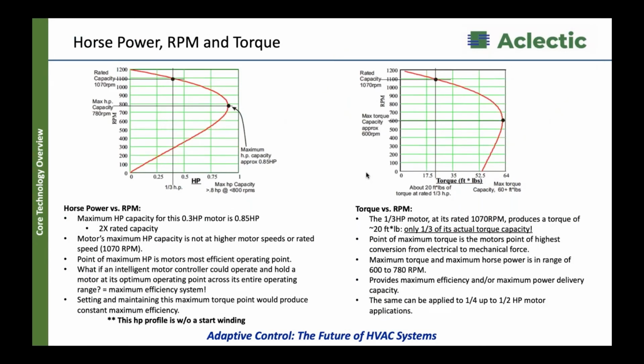I guess I should pause here because I don't want to delve down too deep, but this is a typical picture or plot of the torque and the horsepower on the left, torque on the right. And you'll see a typical PSC motor, independent of brand, a third horsepower motor has the potential to go all the way up to like 2x its power, as long as you don't go over the nose of that curve and tumble down into stall.